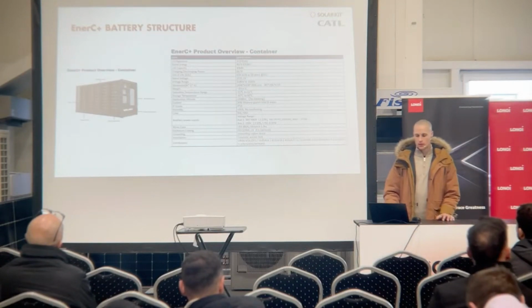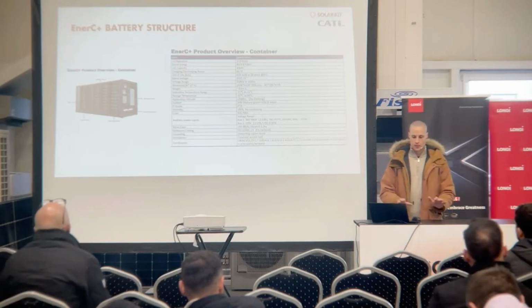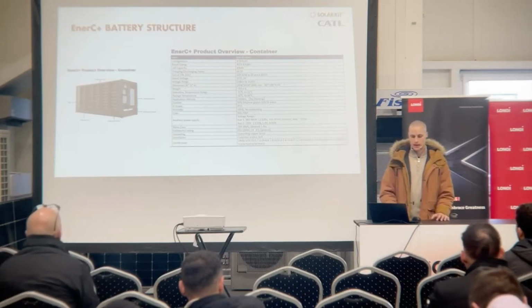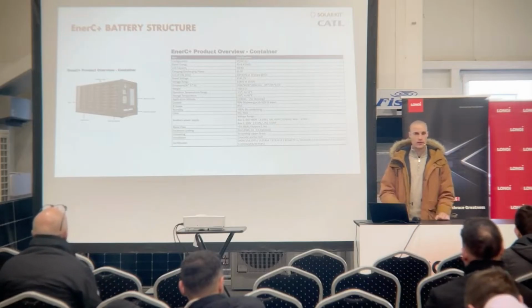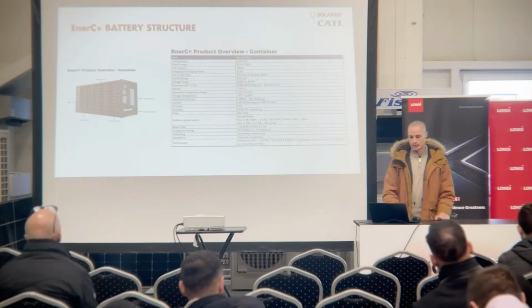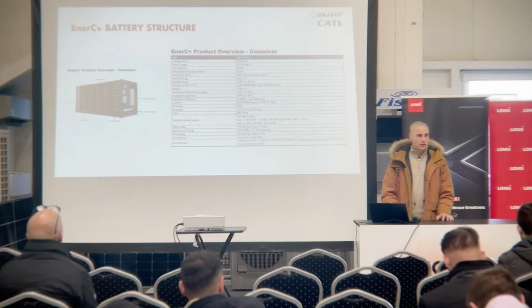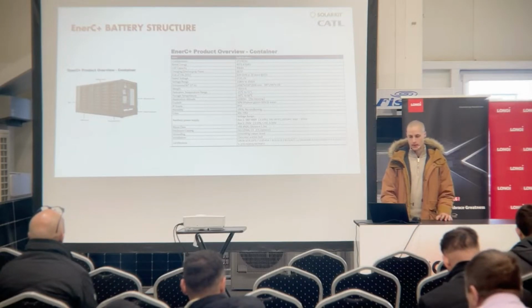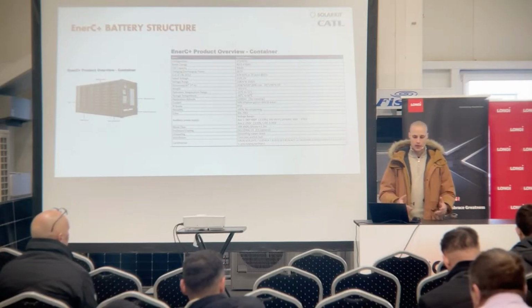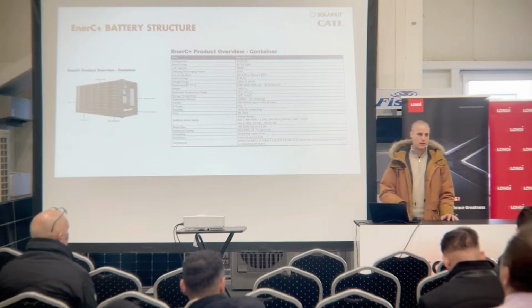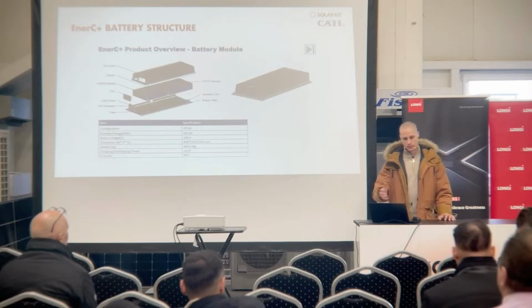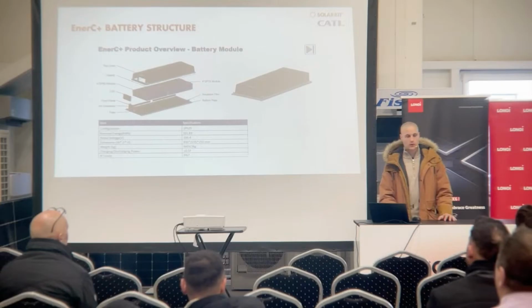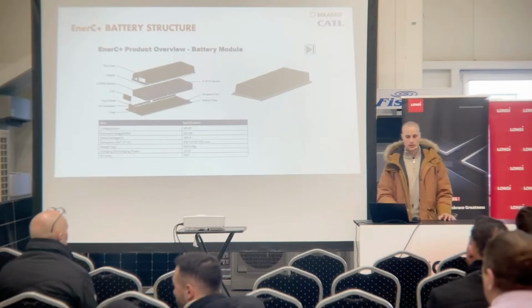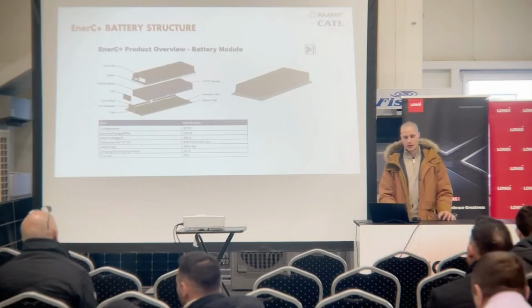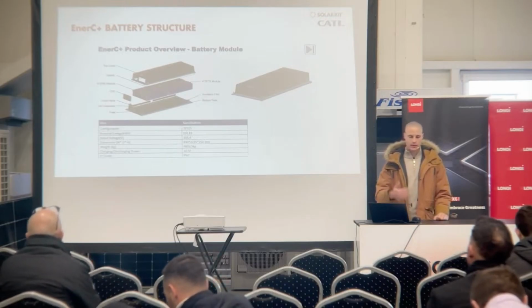For the EnerC+, the container solution, it's a 20-feet container packed fully with the same liquid cooling cells and packs — basically just a bigger solution, but based on the same structure as the cabinet. This one is almost 36 tons, so you really need a big crane to operate it and a really good foundation. You have to make sure you have a proper foundation for this almost 40 ton container before building the site, to maintain its place. The battery packs look similar to the previous version — 100 kilowatt-hour each, with the container packed fully with them, based on the same structure, same liquid cooling plate on the bottom, and the same cells from CATL.